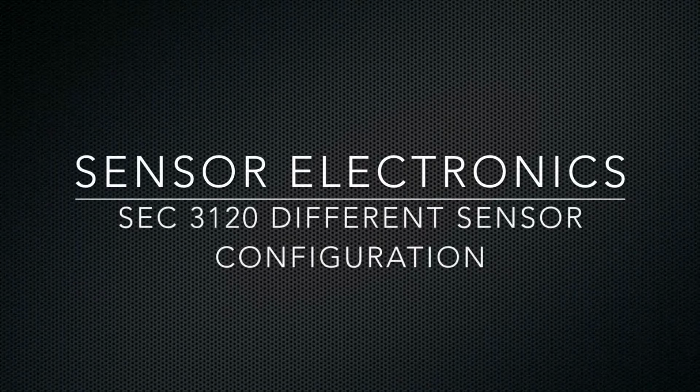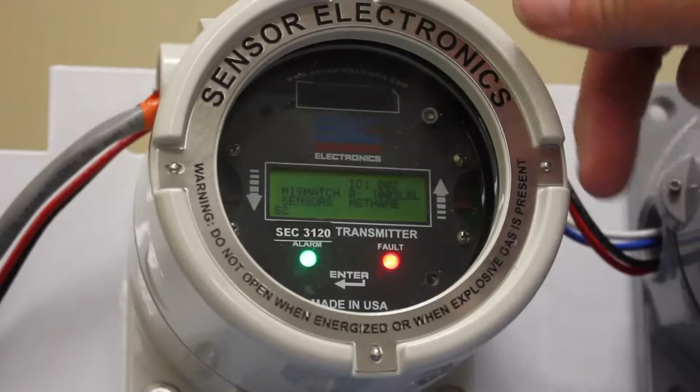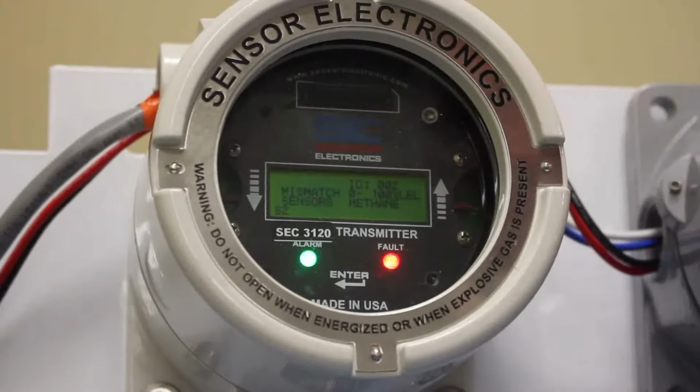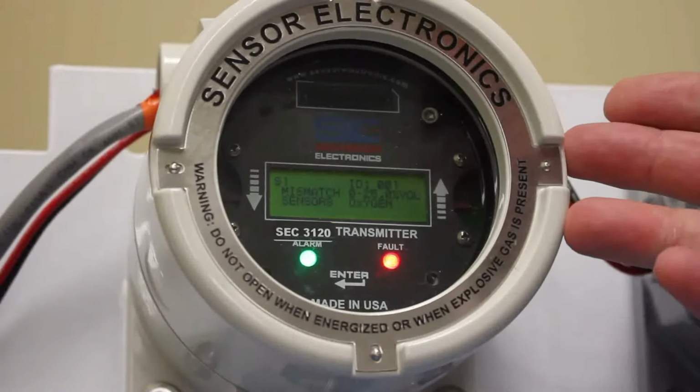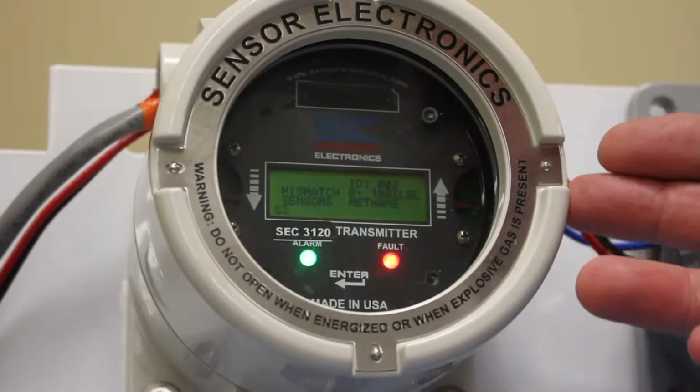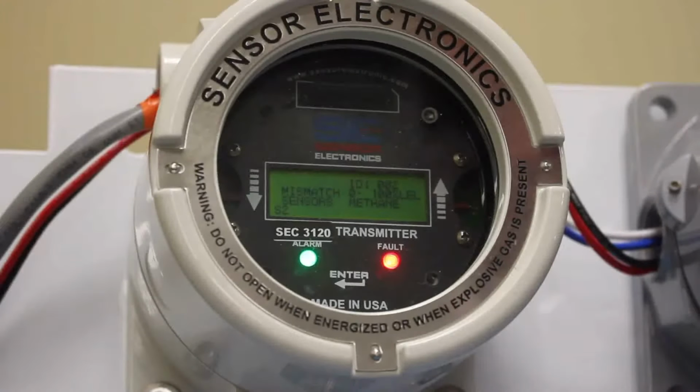In this video, what we've done is we have the 3120 transmitter, the dual transmitter, and we have two sensors hooked up to it. So we have one oxygen, the SEC 3000 oxygen sensor, and then the methane sensor. And so when we first powered it up, what comes up is that the sensors are mismatched. It's typically a default setting in the 3120 transmitter.